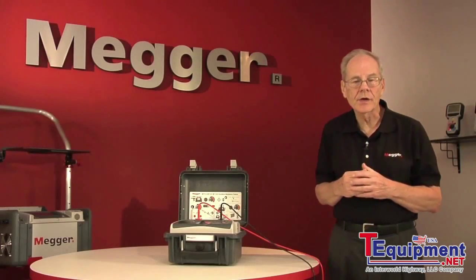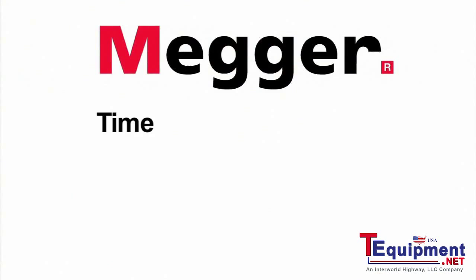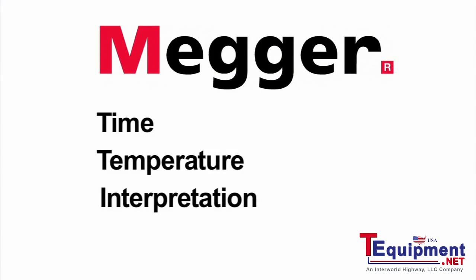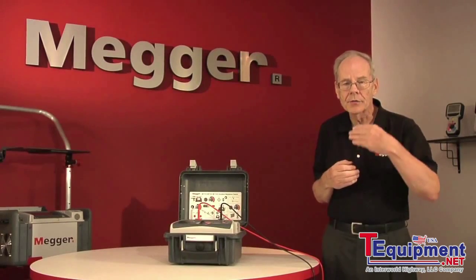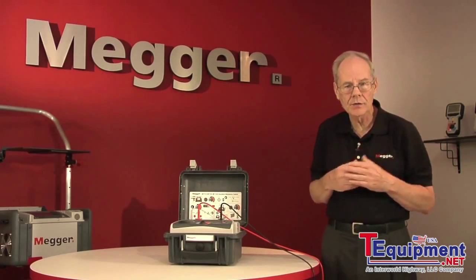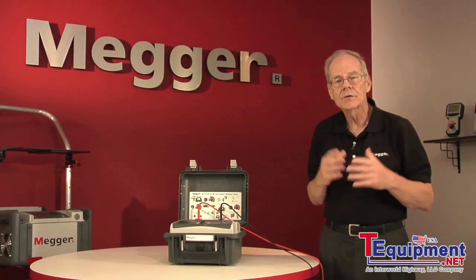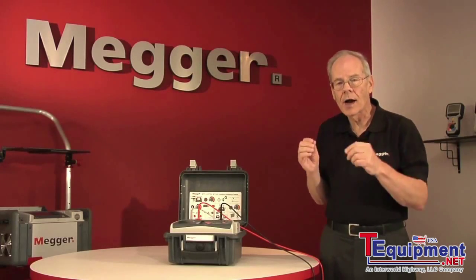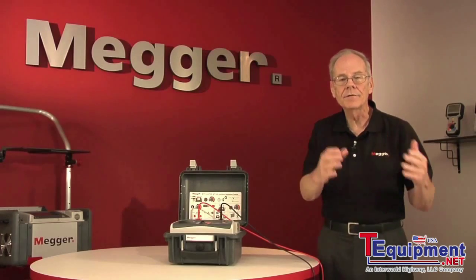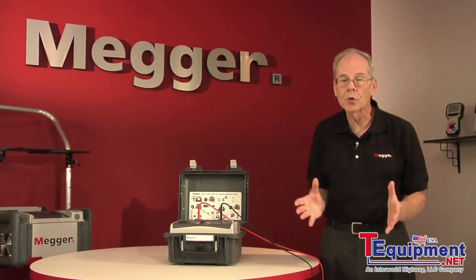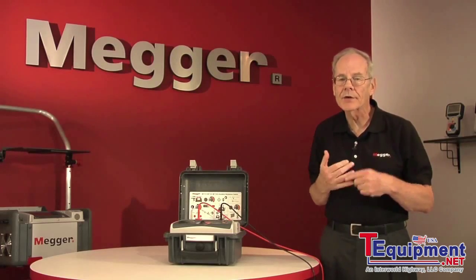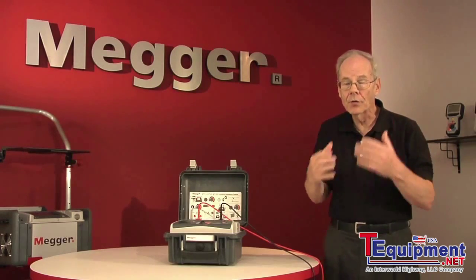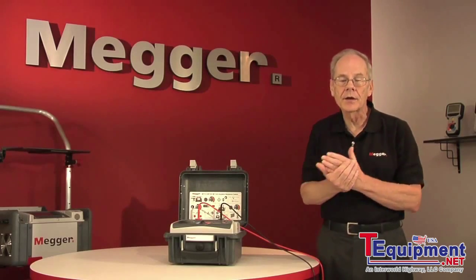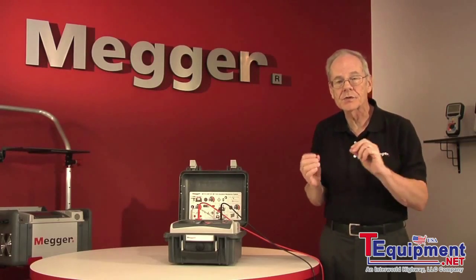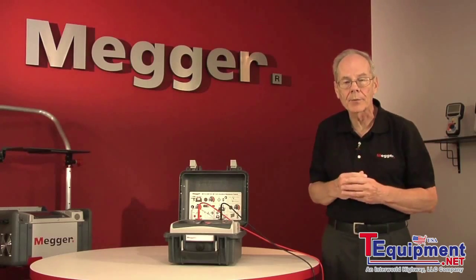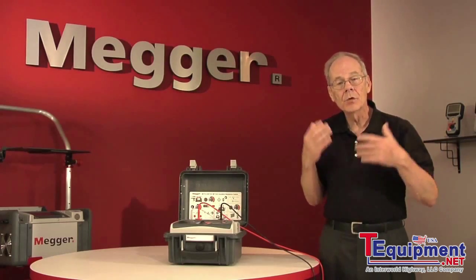A limitation of the spot reading test is that it's dependent upon time, temperature, and interpretation. Because the test item is charging and the readings are changing as the item goes to full charge, time is important, and the time at which the reading was taken influences the actual number that gets recorded. Temperature is also a factor. Temperature affects insulation notably and consequently has to be taken into account, and for record purposes typically adjusted to a common temperature base. And thirdly, you end up with a number.